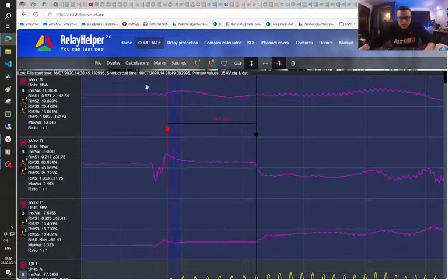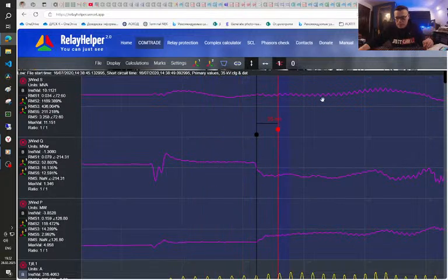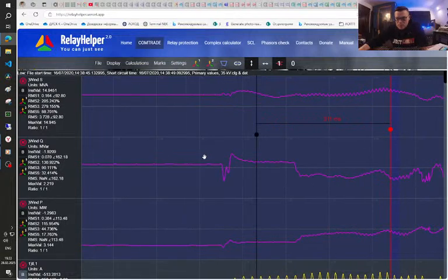And also on the top we can see apparent power, and in this case the RMS instantaneous value is 9.9 MVA, and during the event it changed around this value. So in this area where reactive power started to be produced, we can see 10 MVA and so on.